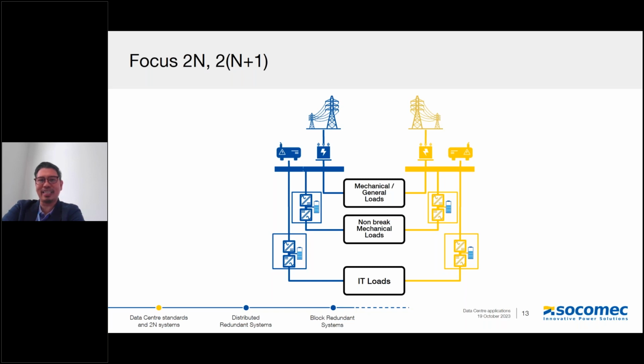Some of the mechanical loads don't need it because they will not create any disturbance, because as you know, temperature doesn't rise instantly. On a chilled water system, the water temperature means they can allow a few seconds of power loss when the genset kicks in, so in order to restart them it will not have much impact, compared to the critical cooling devices like chiller pumps, the controls, or the FCUs that need to be always on in terms of UPS protection.